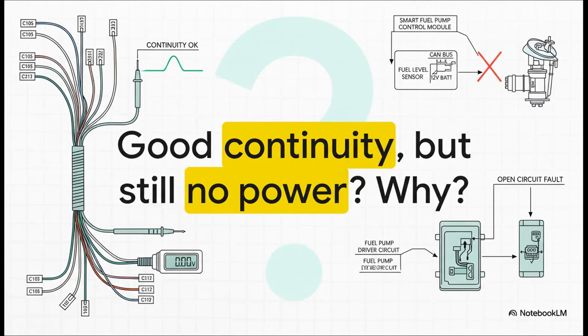So that leads to the big what if, right? What if your wires check out perfectly? You've got good continuity, but you know for a fact there were 0 volts at that pump connector. So where did the voltage go? Well, now we know we're not chasing a broken wire. Now we're looking squarely at suspect number 2.